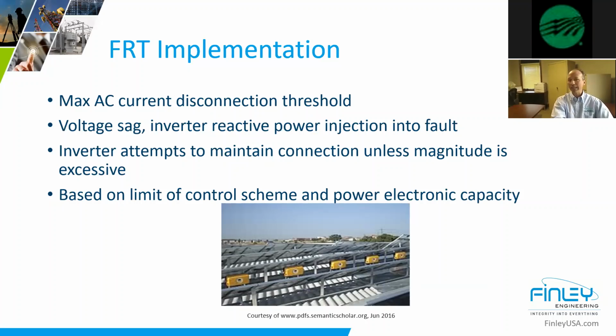So I know this has always been a concern with linemen who start asking, hey, how do I know when I go up to grab that line when it's down at the sub that I'm okay? Well, your inverters should be disconnecting and cutting loose. And the question is, yes, in a voltage fault condition, they should be coming off according to the 1547 standard. But in those minimal events - this would be the fast impact stuff - those are the ones that are more impactful in this case, but they can feed into the fault. That's really the point of that discussion. And it's based on their design parameters - each one's different.